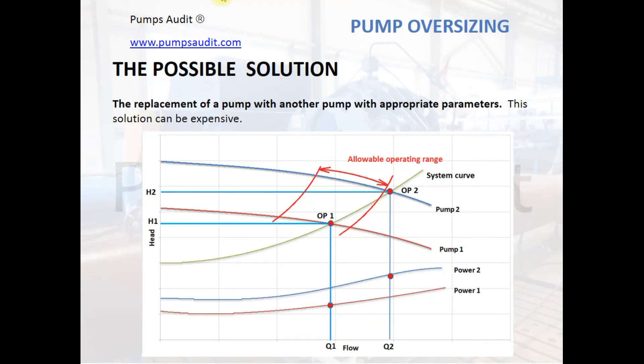Another solution is replacement of the pump with another pump with appropriate parameters — for example, one with less head. This solution can be expensive but it is much more effective. If we replace pump 2 with pump 1, pump 1 will operate within its operating range without energy loss.